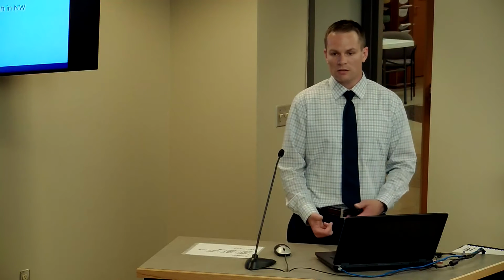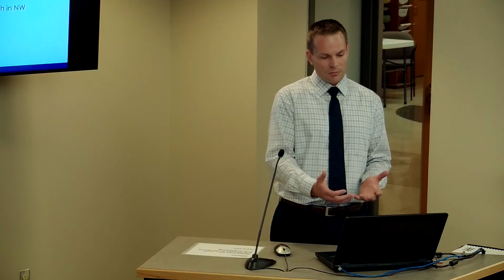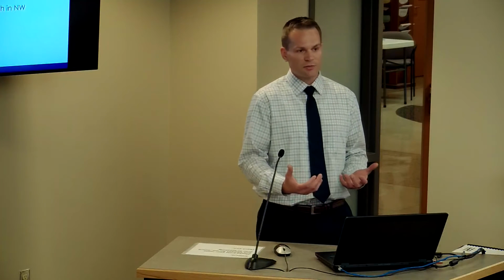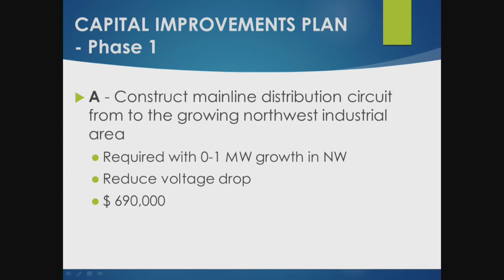For phase one, project 1A: if we do end up getting some load immediately in the next year or two, up to a megawatt, how would we handle that? There would be some voltage issues on the west circuit. This isn't a band-aid, it would be useful - it's hardening your distribution infrastructure, and you're not going to regret that. It essentially addresses voltage drop concerns on the west circuit. At 690,000, it's basically getting you an additional feeder from the existing distribution further out on the existing distribution.